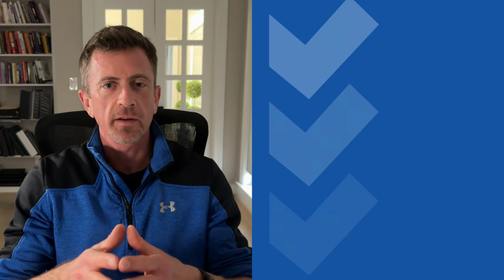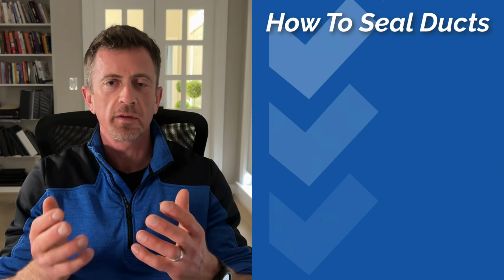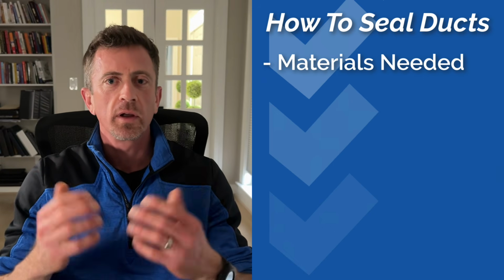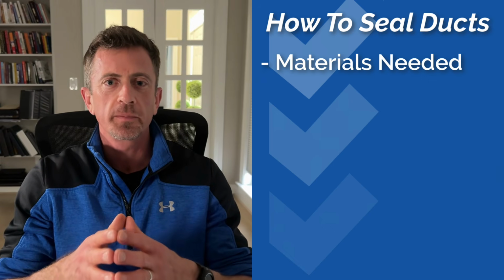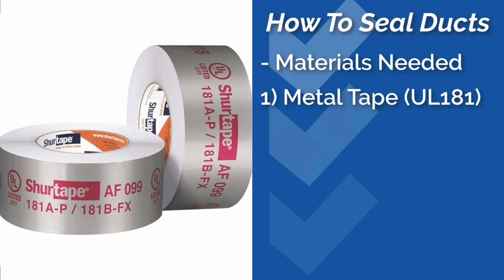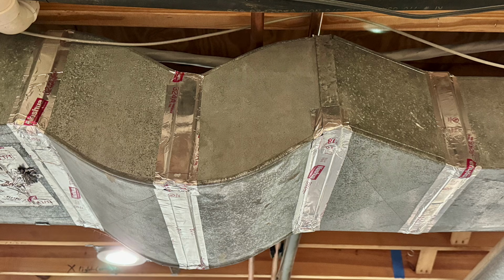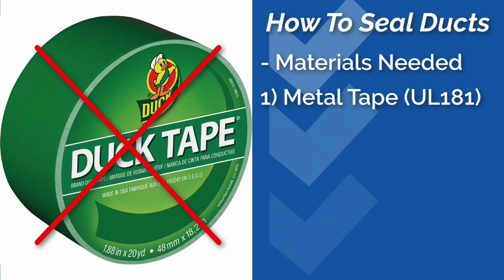Okay, let's get practical now. How do you actually find and seal all these pesky duct leaks? Well, you need the right materials to start off with. The first one is metal tape or foil tape. This is a UL 181 rated metal tape that's for duct systems, not duct tape. I know they call it duct tape, but it's not actually for ductwork.